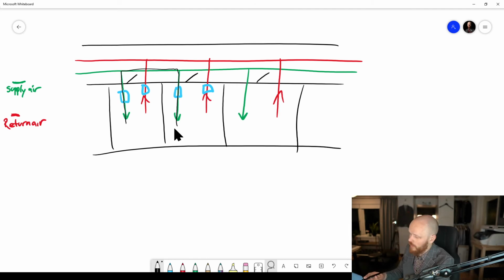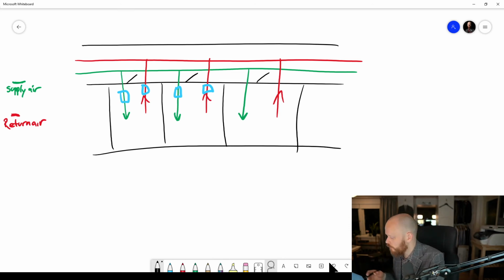And that means it's going to be reflected inside the silencers quite a lot. So when you have two silencers with a bend, a change of direction, between them, the sound reduction of the silencers improves a lot. And that means this configuration is the one that is preferable with regards to acoustics.